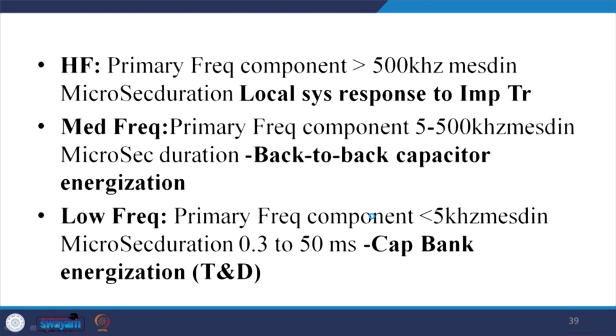For example, if it is high frequency, the primary frequency component will be above 500 kilohertz, with microsecond duration, a local system response to an impulsive transient. For mid frequency, the primary frequency component will be in the range of less than 500 kilohertz to 5 kilohertz, with duration in tens of microseconds; back-to-back capacitor energization may cause this mid frequency oscillation. For low frequency oscillation, the primary frequency component is below 5 kilohertz, and this is generally again a large capacitor bank energization.